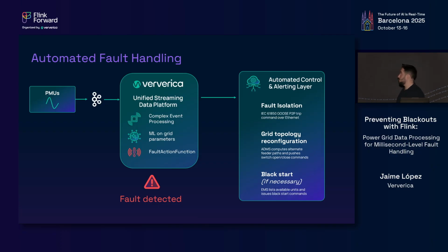So in these 250 milliseconds, you're already going to have your fault isolated. The power line that fell down or that went on fire is isolated from the grid. Nothing is connected to it so that the grid doesn't react to it. And you can, within a second, calculate how the grid needs to adjust to avoid this path that now doesn't work. Do I need to go through a different path, or do I need to activate something else? So in 1 second, you can have these alternate feeder paths computed, and you can be starting or stopping the generators that need to patch for this.